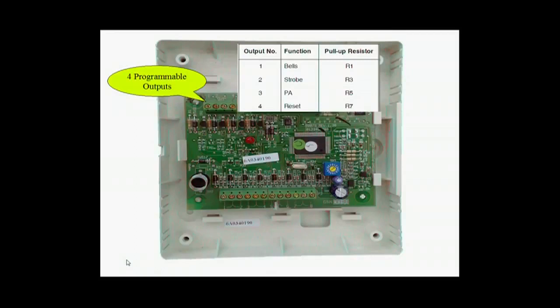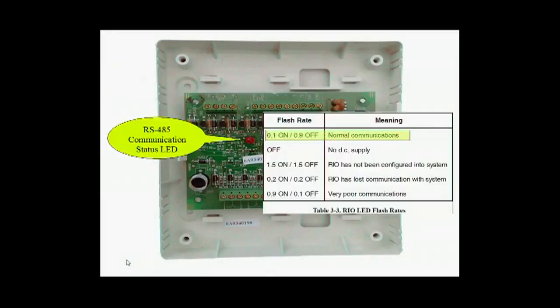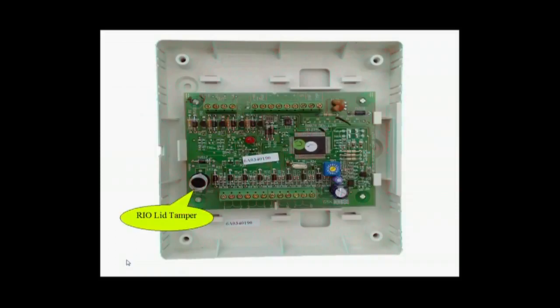These can of course be reconfigured under menu 53 program outputs. To the middle of the board we have the RS485 communication status LED. Under normal communications it is highlighted at 0.1 of a second on and 0.9 of a second off.